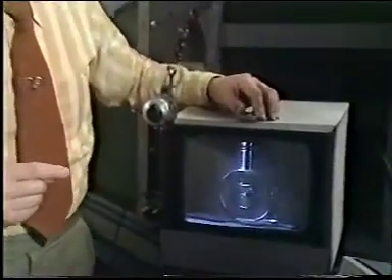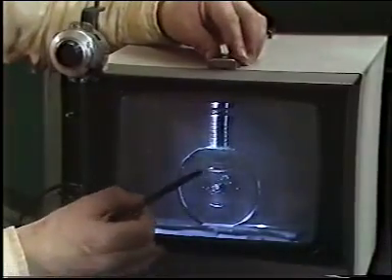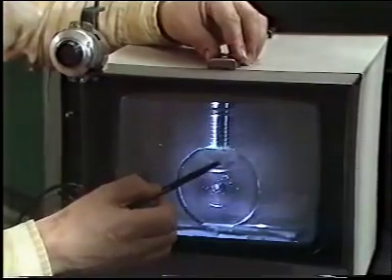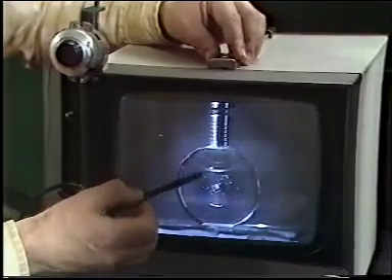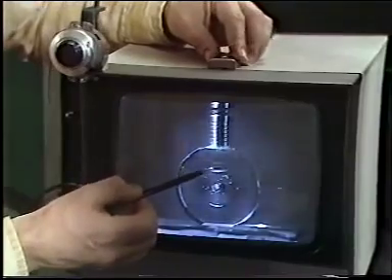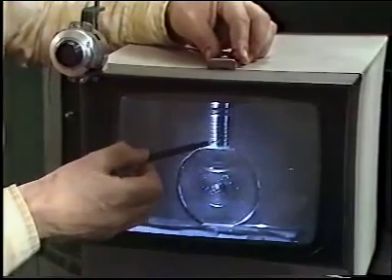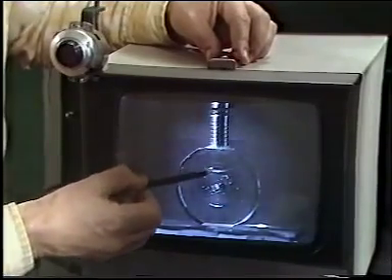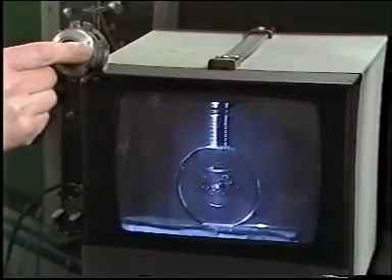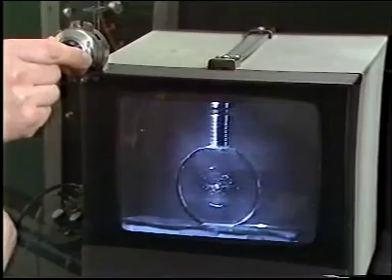Now, at the moment, you can see the wave packet or train of pulses just here. And in fact, the light bands you can see are the peaks of the stresses in the ultrasonic wave. So each of these is a cycle or a wavelength in the glass. At the moment, the light is being flashed just a little bit later than the transmitter transmits from that point, so that by the time the wave gets to there in the block, we flash the light and we see it stationary. Now, if I turn this knob, we can increase the delay, and the wave appears at later and later times as it propagates through the block.